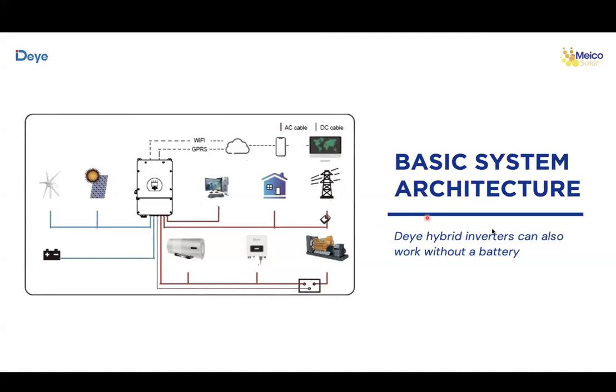I have another question from David: can one inverter have a connection to all three phases? Yes, one inverter can have a connection for three phases. So you will have both options - you can have only a single phase inverter, or you can fit three equipment together to do three phase, though that's not the easiest way. There are also dedicated three phase inverters, and I'll show you the connection diagram in a few seconds.